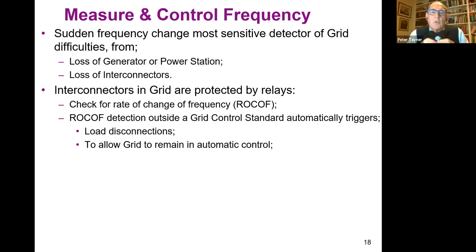And there are grid control standards in each country. Countries that are joined together agree the grid control standards between one another to ensure that we're working in a common way. Detection of a ROCOF causes people to trigger load disconnections or to allow the grid to remain in automatic control by compensating by increasing generation.